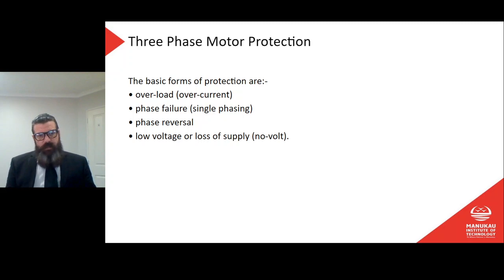So the basic protection performance covers overload, so that's our high current, and phase failure, what we call single phasing. So if we've got a three-phase motor and we lose one of the phases, that motor still may operate on two phases, but it's going to draw a heck of a lot more current. Think about it as losing a cylinder on your car.